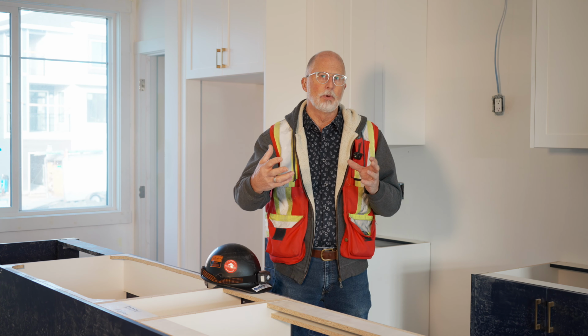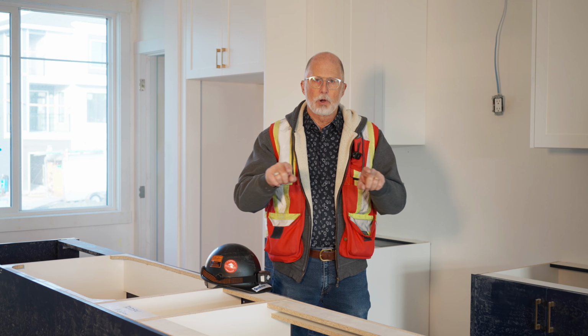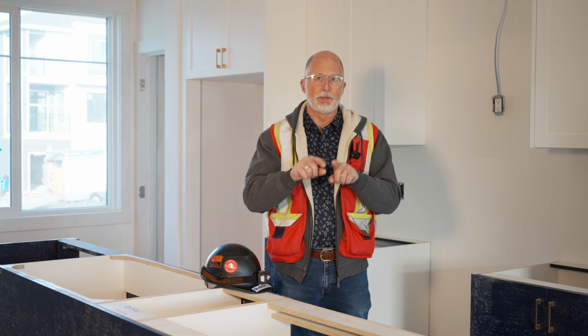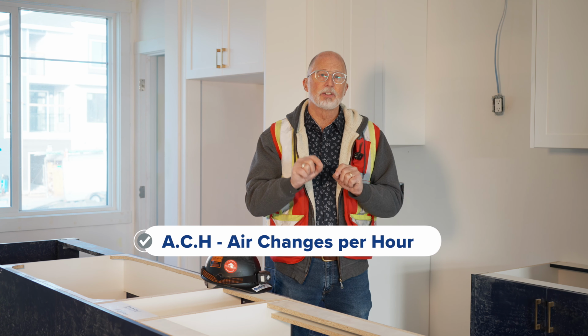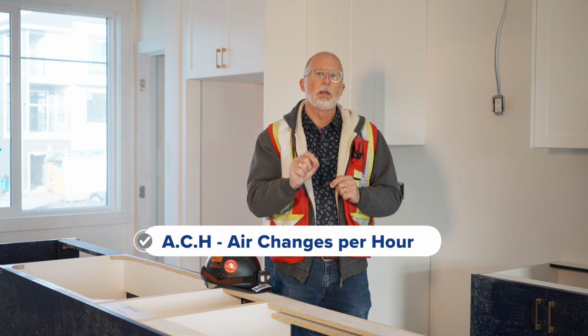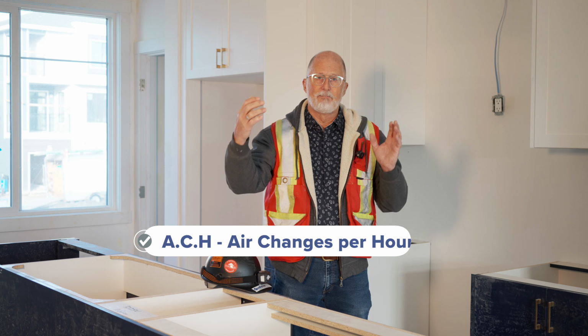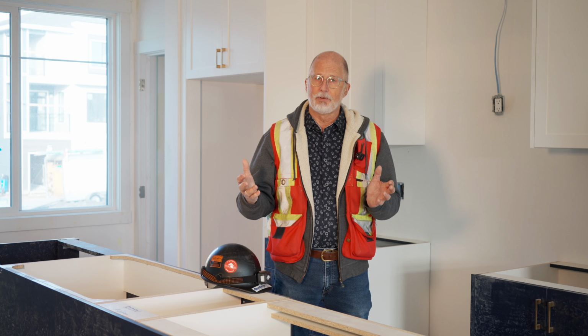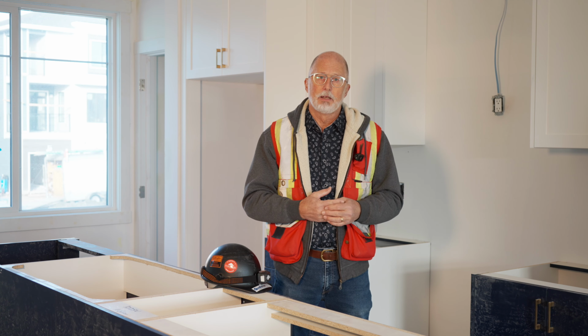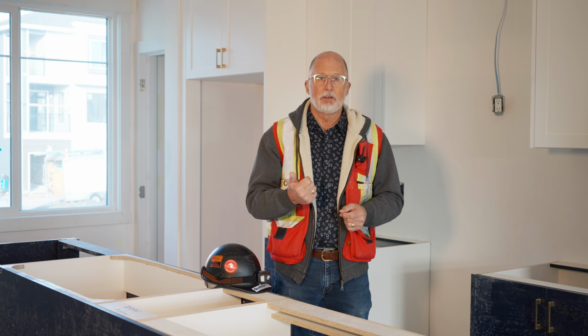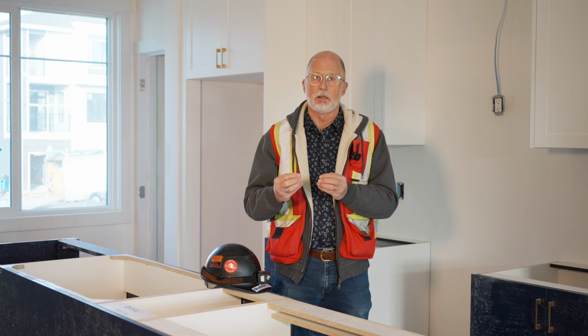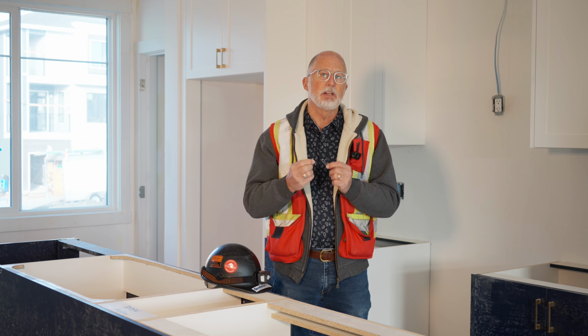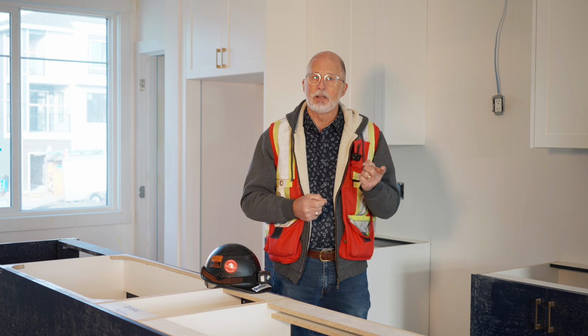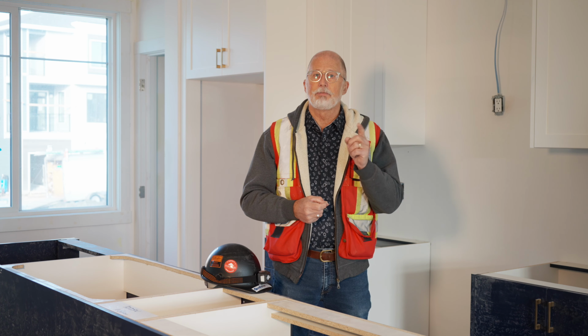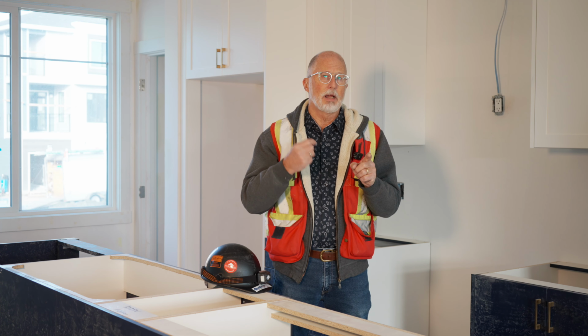So we're not dealing with per square foot leakage, we're dealing with ACH, or air changes per hour. When we deal with air changes per hour, the volume of the unit makes a big difference. So an average volume for a single family home could be 25,000 to 30,000 cubic feet. So that's exchanging the air. If you have a 1 ACH, that's exchanging 25 to 30,000 cubic feet every hour.